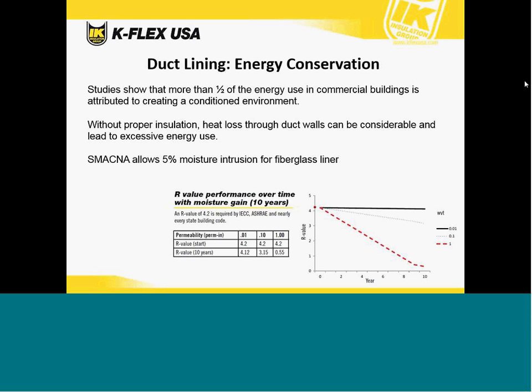More than half of the energy use in commercial buildings is attributed to creating a conditioned environment. Without proper insulation, heat loss through duct walls can be considerable and lead to excessive energy use. SMACNA also cites a 5% moisture intrusion for fiberglass liner, and as discussed earlier, that moisture intrusion will reduce the performance of the insulation material over time. So again, as with pipe insulation, we want to keep duct liner clean and dry to keep the performance stable over time and to reduce any instances of mold or fungal growth inside the ductwork.